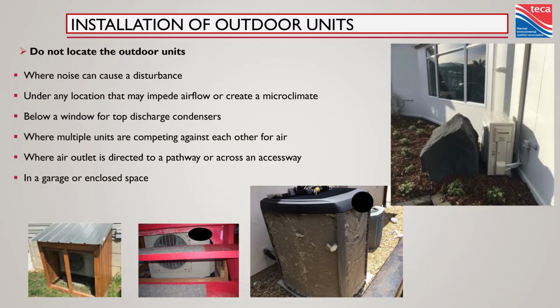So air source heat pumps get their heat from the outside air or reject their heat to the outside air. So make sure it's fresh air all the time. Don't put it in a confined space where it's gonna recycle the same air over and over again. You're just gonna start going down a rabbit hole you'll never come back out of. You want to avoid having one heat pump blowing its air into another heat pump because you've already taken heat out of that air. That next one's going to have a tougher job. You want to make sure that you avoid placing these things where they're going to get snow landing on them, or if they're cooling the house, you don't want a hot air vent pointing at them.